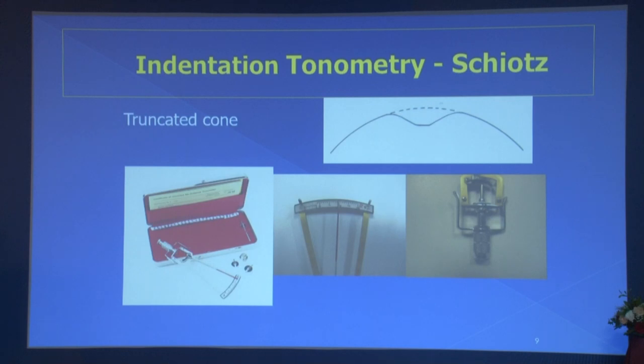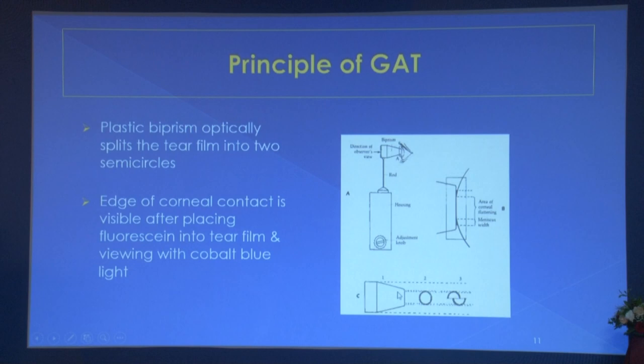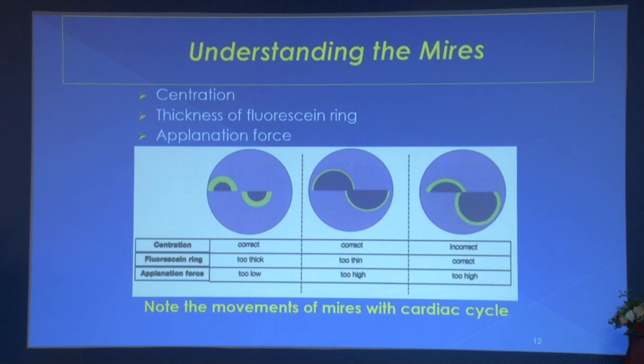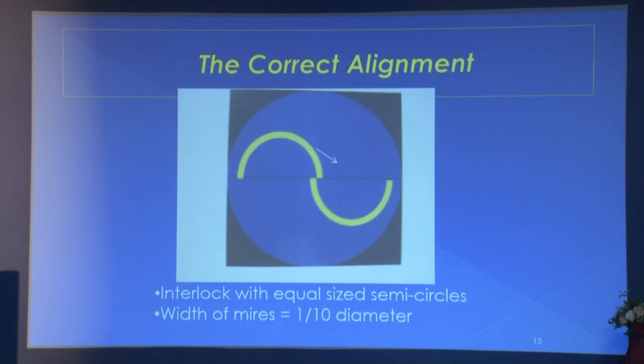Indentation tonometry is problematic when ocular rigidity is high or very low. The Goldman applanation tonometer has a plastic biprism which optically splits the tear film into two semicircles. The edge of corneal contact is visible after placing fluorescein into the tear film and viewing with cobalt blue light. Understanding the mires is based on centration, thickness of the fluorescein ring, and applanation force. The two semicircles should interlock with equal size, and the width of the mires should be one-tenth of the total diameter.